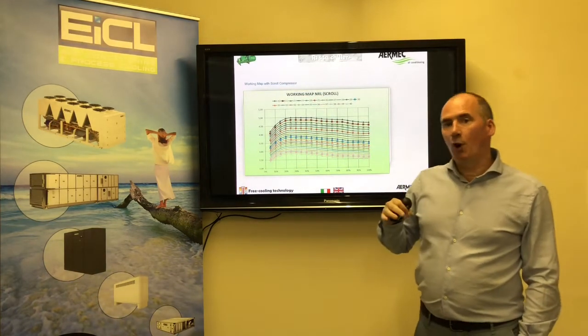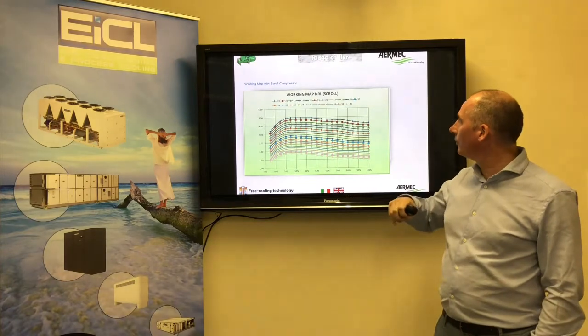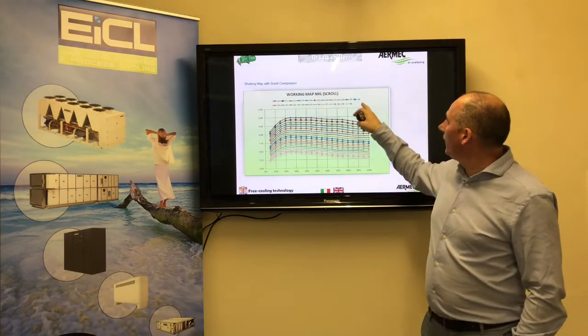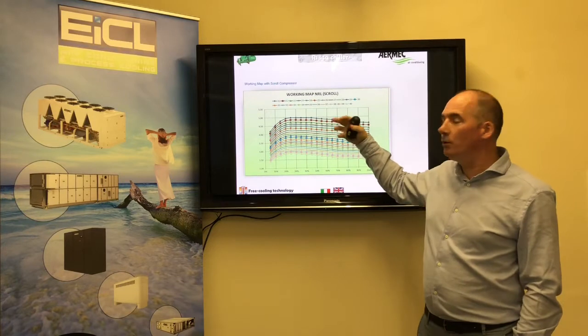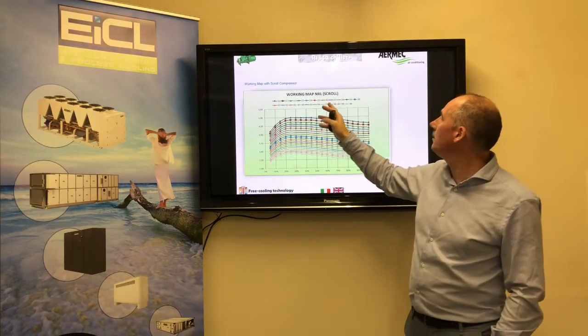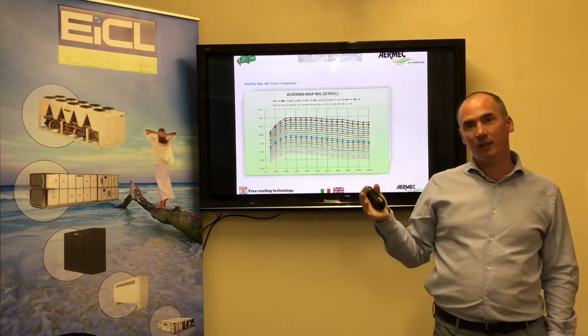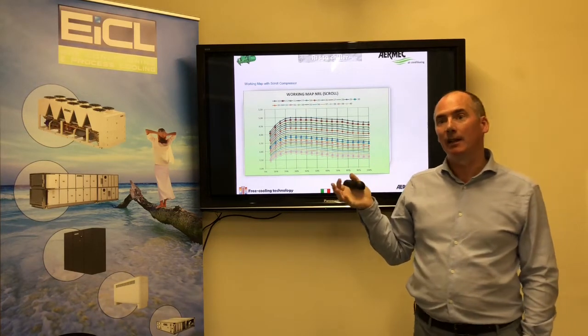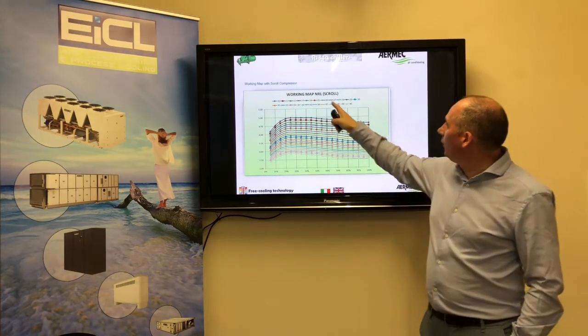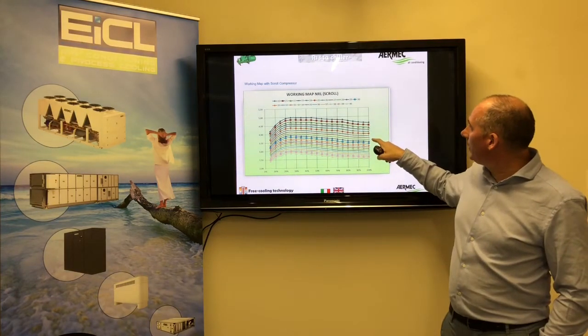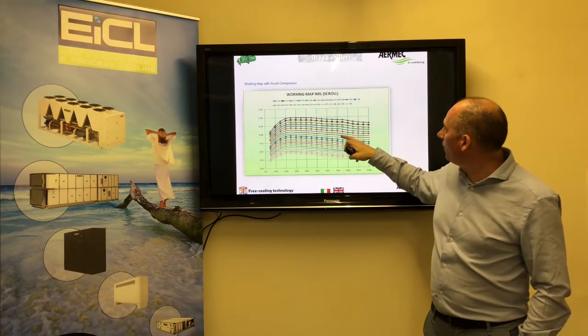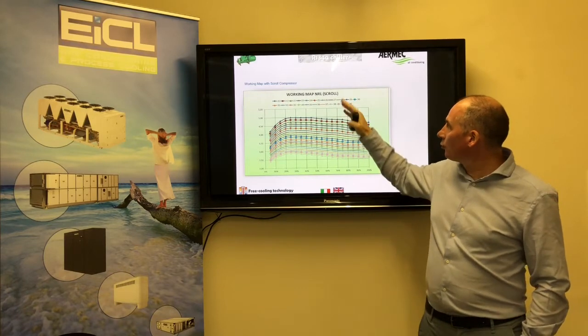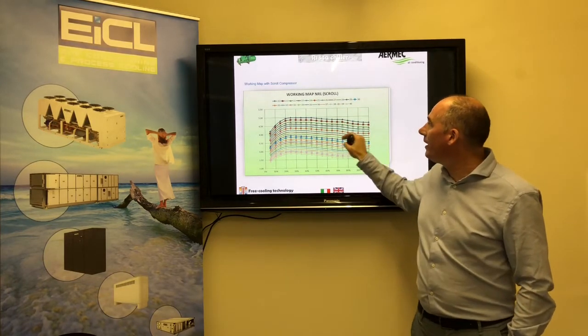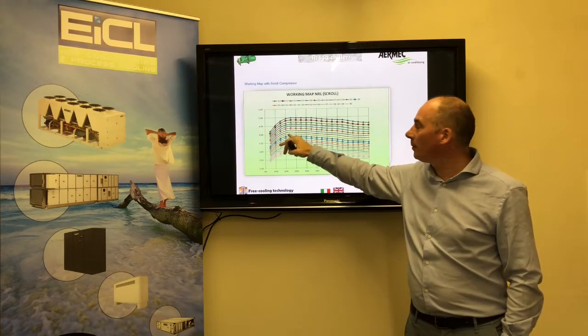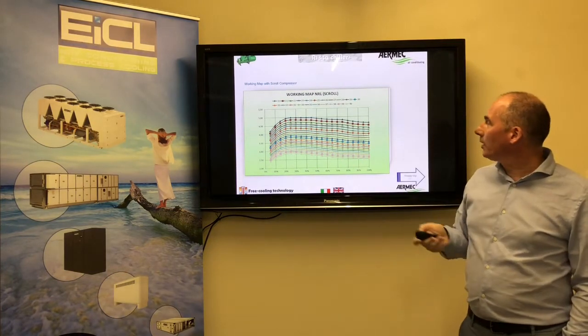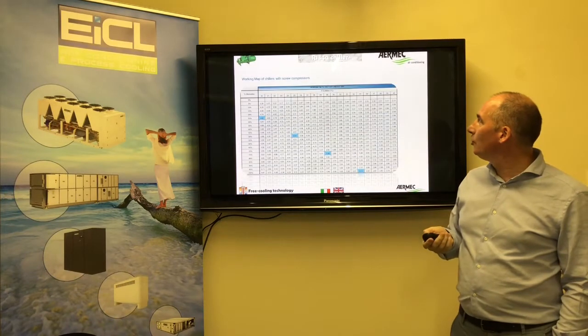So I just want to give you an example of a couple of part load efficiency curves. So you can see various different ambients here. In Ireland we use a design ambient of about 27 degrees C. Typically the hottest day of the year in Ireland is considered to be, I think it's 26.6 on ASHRAE. So if we look at the ambient at 26 degrees C and we follow it up here, we can see the efficiency of the scroll chiller in part and low load is consistently improving almost down to about 20%. We can compare this with the screw compressor.